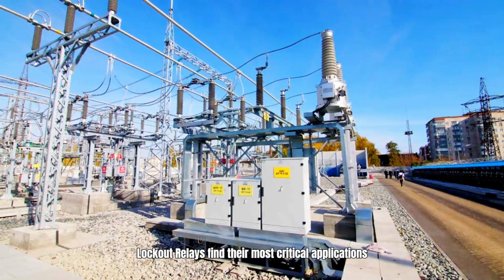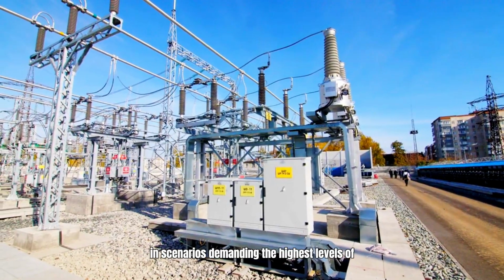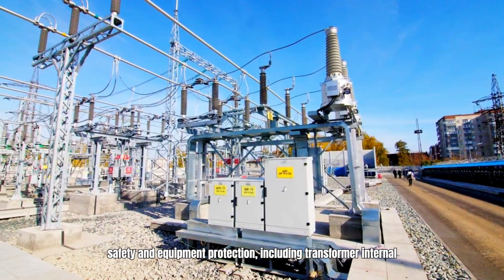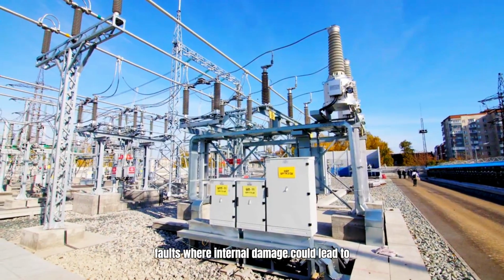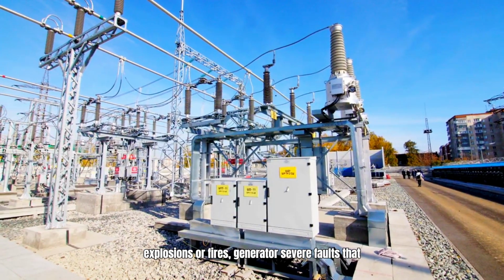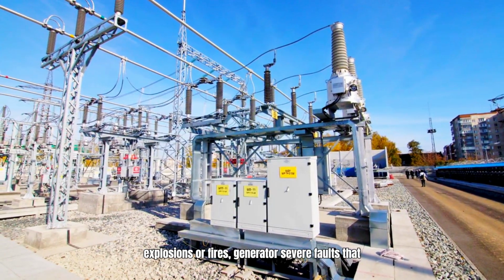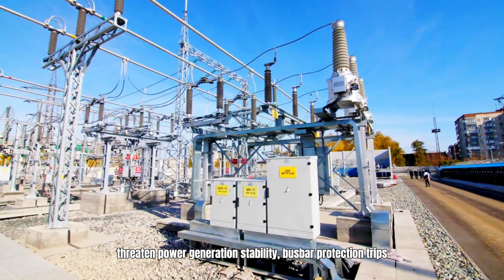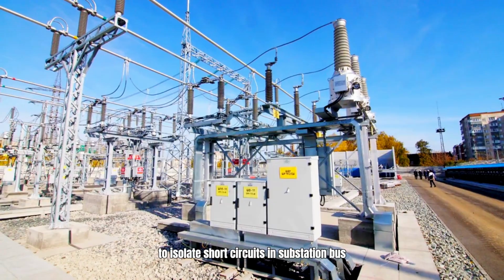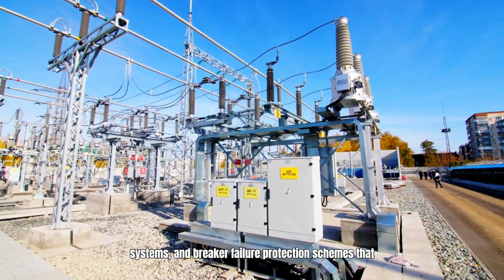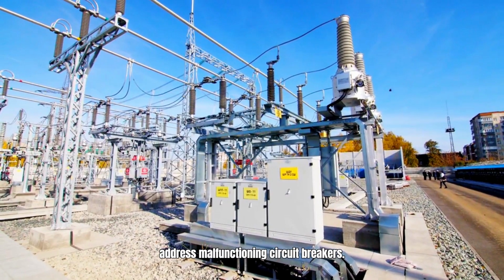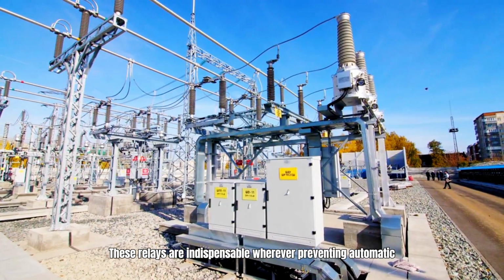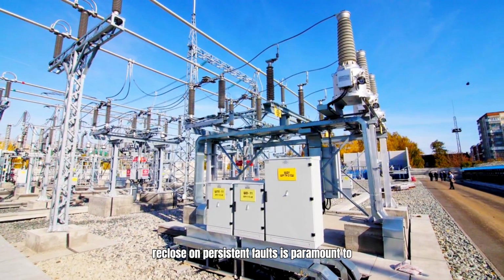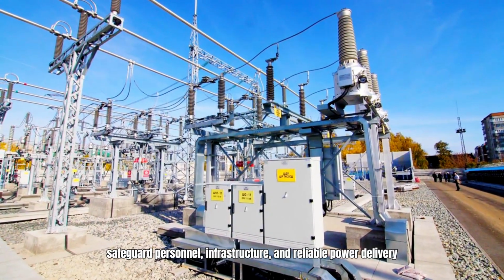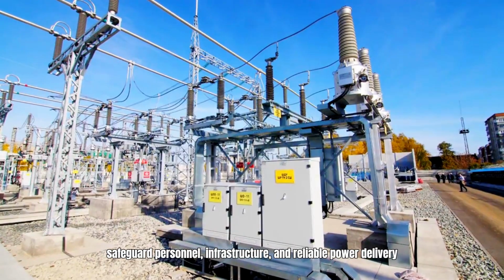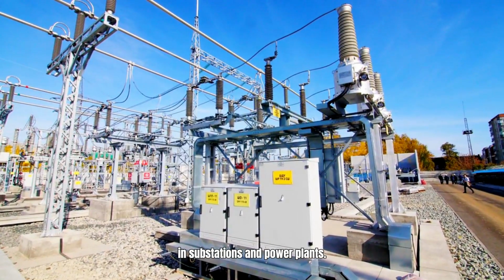Lockout relays find their most critical applications in scenarios demanding the highest levels of safety and equipment protection, including transformer internal faults where internal damage could lead to explosions or fires, generator severe faults that threaten power generation stability, busbar protection trips to isolate short circuits in substation bus systems, and breaker failure protection schemes that address malfunctioning circuit breakers. These relays are indispensable wherever preventing automatic reclosure on persistent faults is paramount to safeguard personnel, infrastructure, and reliable power delivery in substations and power plants.